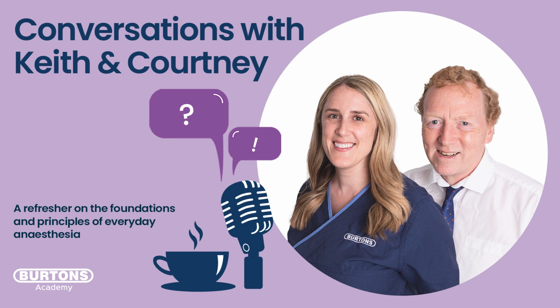Well, the situation you described there is actually where you've had a decreasing signal magnitude over time. So it's probably started off at 120/80 and a mean of 93, your standard stuff. Then, because of either a kink in the catheter or a blockage in the transducer or blood getting back into the transducer, some action has meant that it's lost magnitude of that signal. So it's then gone 110 over 90, and the mean's gone to 97, and then it's gone 110 over 95. So we're diminishing our pulse height, and our mean is always staying in the middle there, but we're losing signal to the point where, very cleverly, I have to hand it to the monitor, it's actually measuring like 81/79. You're actually measuring that, but at some point it just says everything's at 80, and that's why you get 80, 80, 80. And normally you've probably got a blocked catheter or a kinked catheter.